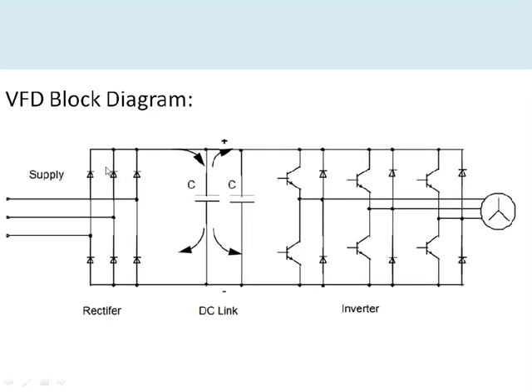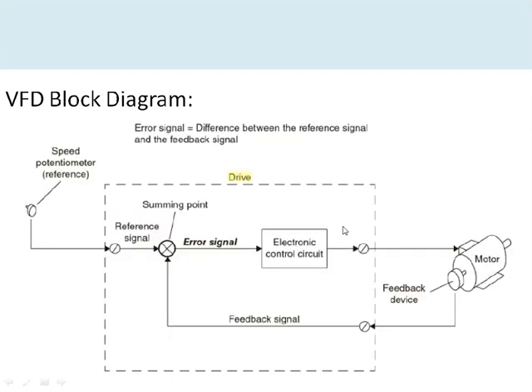This is the typical block diagram of the VFD. A three-phase rectifier takes power from the utility line and converts it to DC. The DC link capacitor bank serves two purposes: it reduces the ripple in the DC and acts as a buffer for the inverter. The inverter is the most important part of the VFD — it converts DC back to AC, and by varying frequency, it controls motor speed using complex processor algorithms.